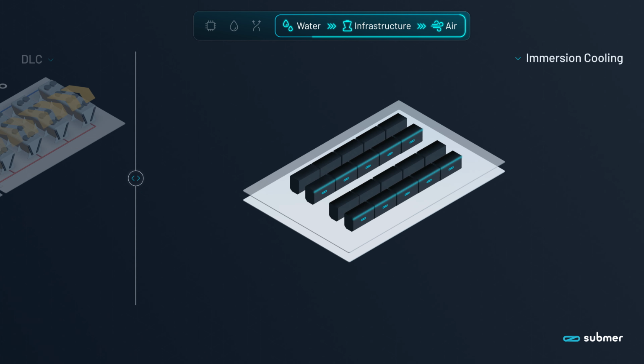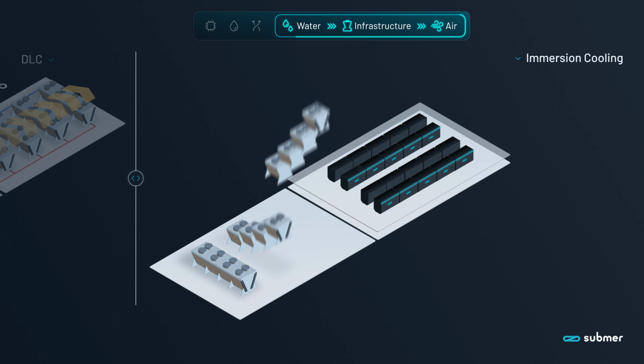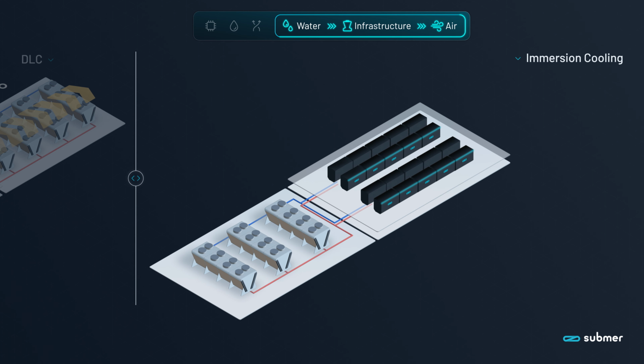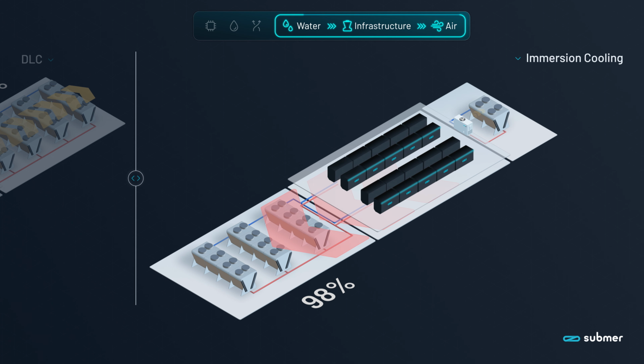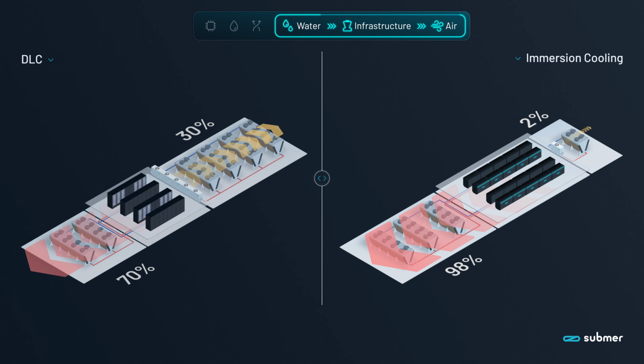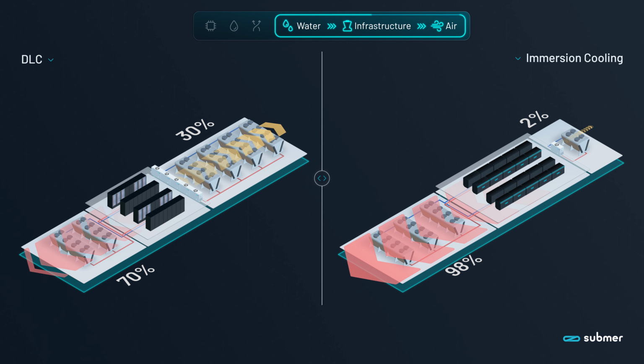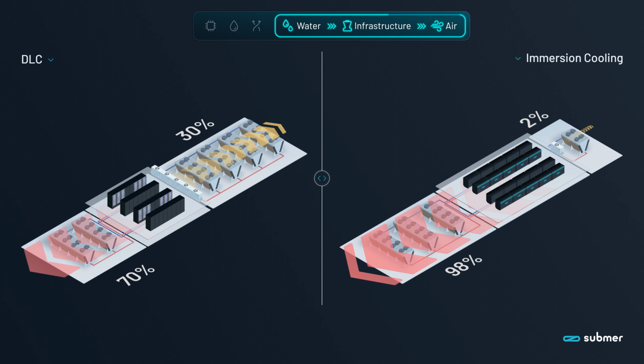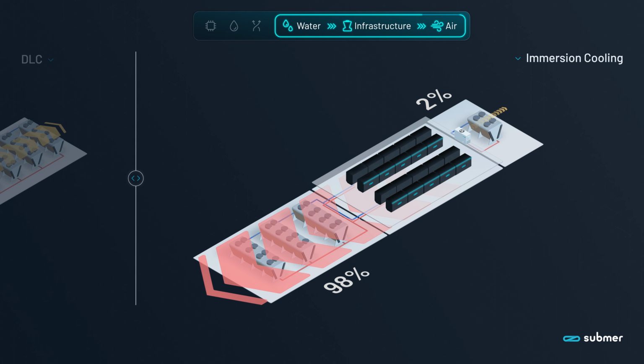For immersion cooling, the heat rejection system for the secondary fluid is relatively larger. However, the infrastructure related to air cooling is significantly smaller thanks to the very little capacity needed. At this point, the heat originated in the chip and other components has been released. While both technologies have a similar footprint, immersion cooling is far more efficient as it captures nearly all available heat. Though not discussed here, this makes immersion cooling ideal for heat harvesting and reuse.